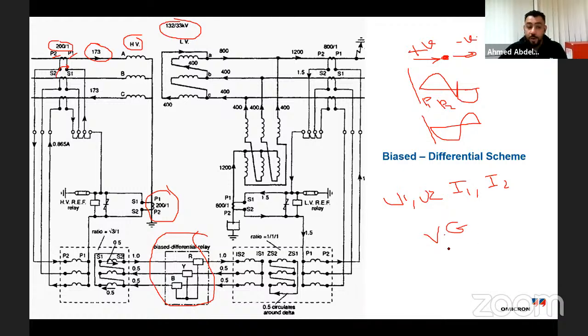So if I have a transformer of vector group 1, let us say that I have a phase shift between the two sides, side 1 and side 2, by an angle of 30. The current on the other side lags the current on the high voltage side by an angle of 30, so it will be minus 30. If I give the differential relay two different currents, with a different magnitude and a different angle, at the end the differential relay will detect a current and it will give you a trip even though the system is stable.